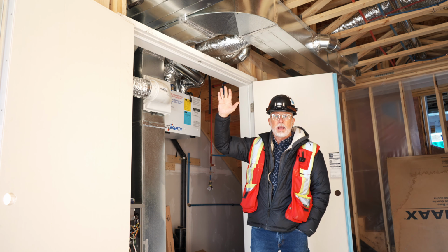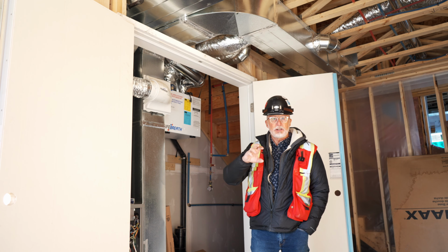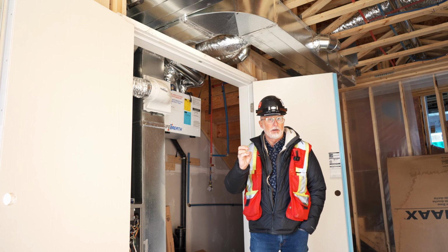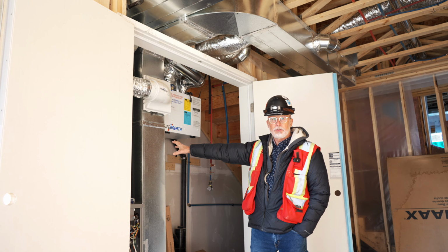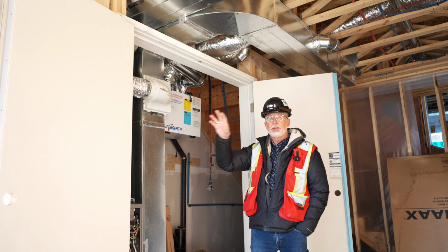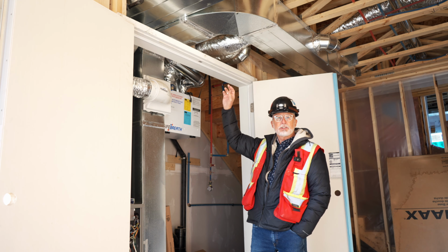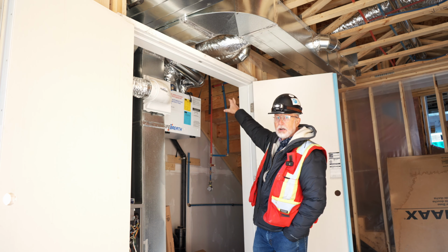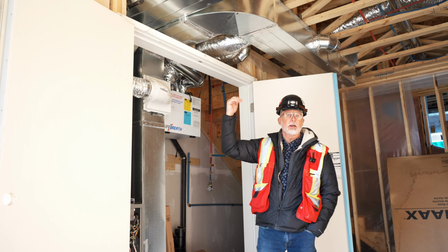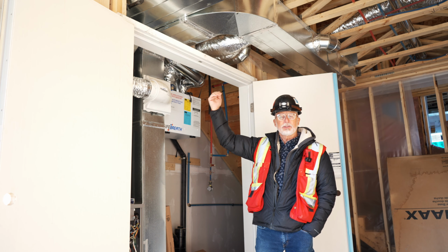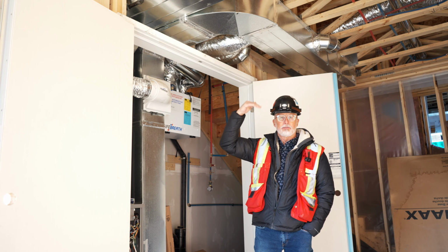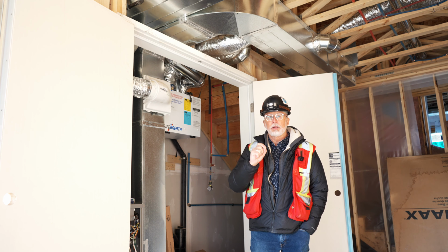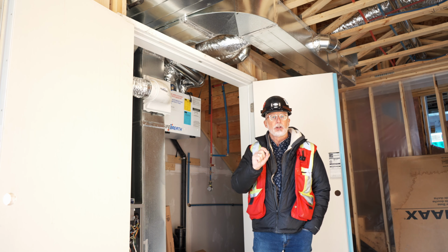of the house. So now everywhere there's a bit of an air pressure differential, for instance stack pressure, mechanical pressures, or even wind pressures for that matter, you will have a pressure in the closet or in this room here that is different than the garage. You'll also have a pressure difference in the connection all the way up. So not only do you have to make this box airtight, as you move through, you have to compartmentalize so that the air that's in here doesn't interconnect either with the floor on the next level or the floor above that.